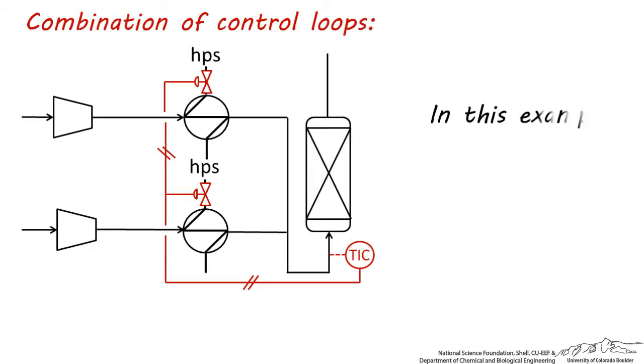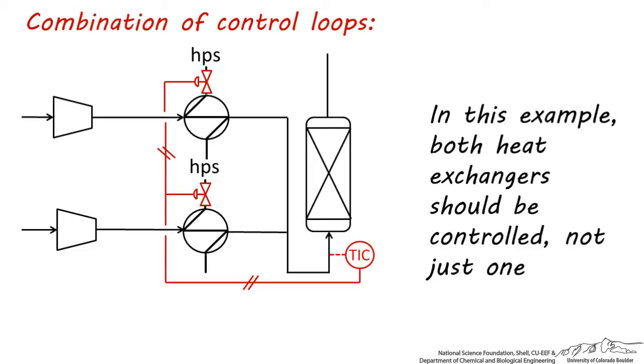As you might expect, the high-pressure steam going to both of these heat exchangers should be controlled, and not just one. This is because these streams mix before the reactor, and there shouldn't be a large temperature discrepancy between them. So this is a suitable control system for the inlet temperature going to R101.